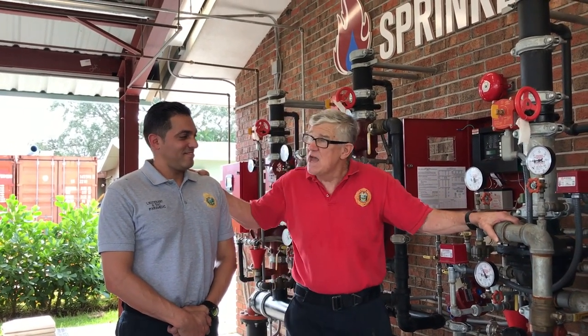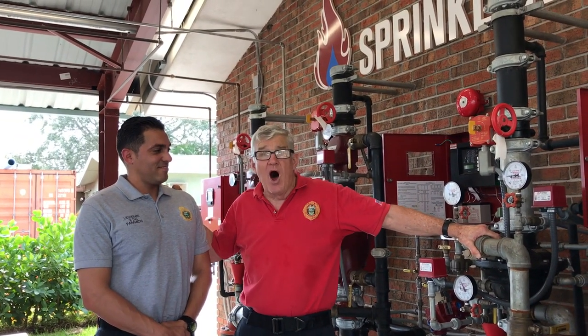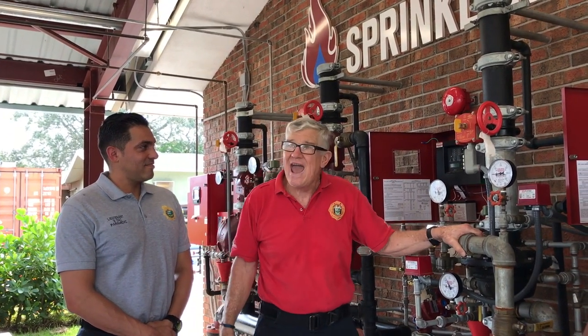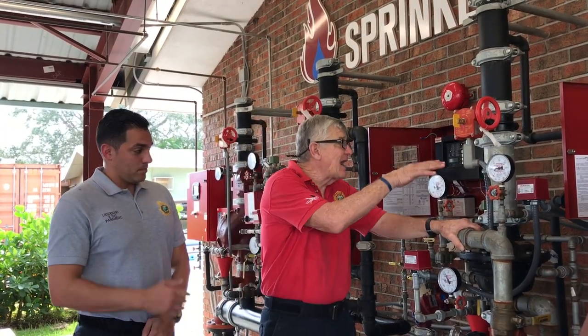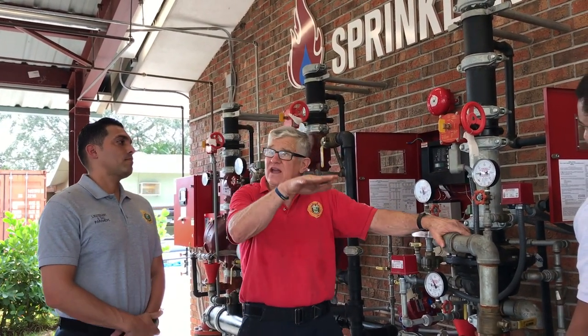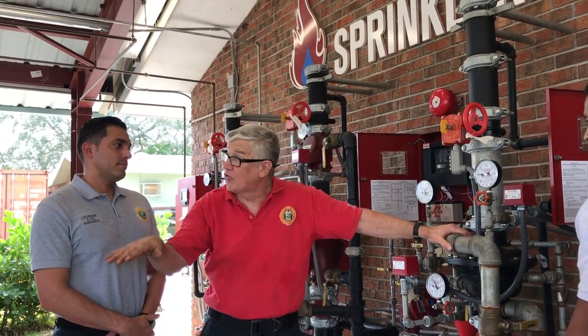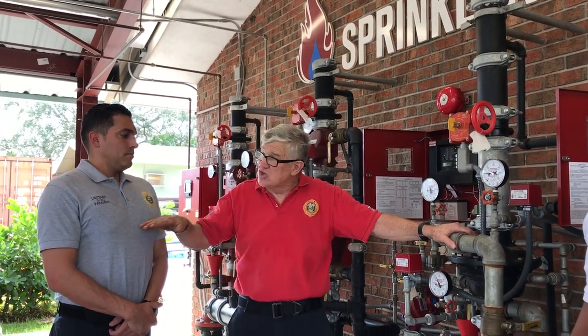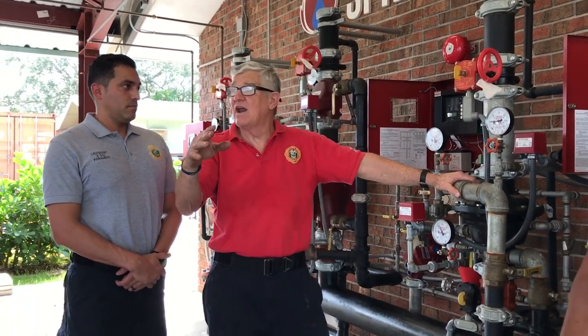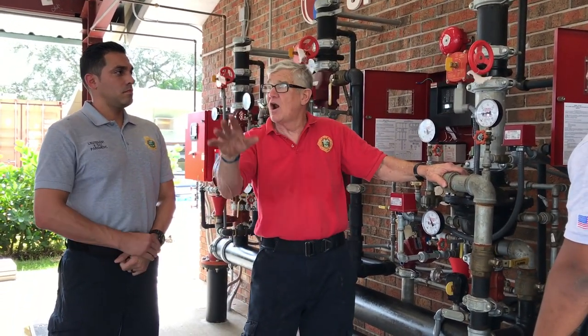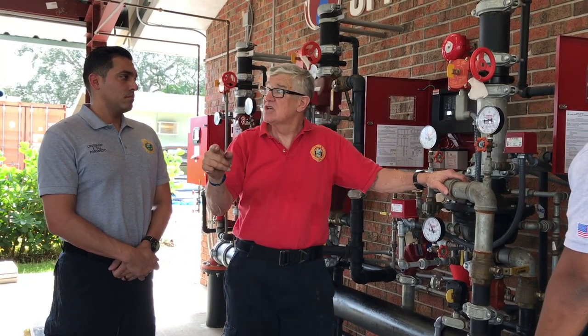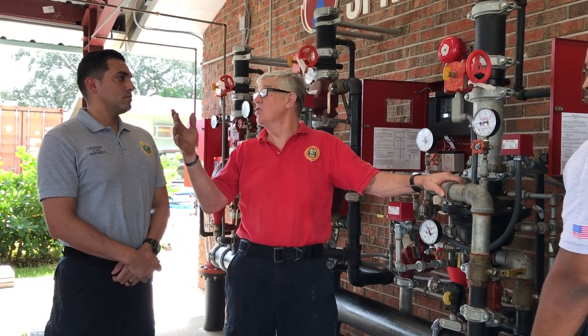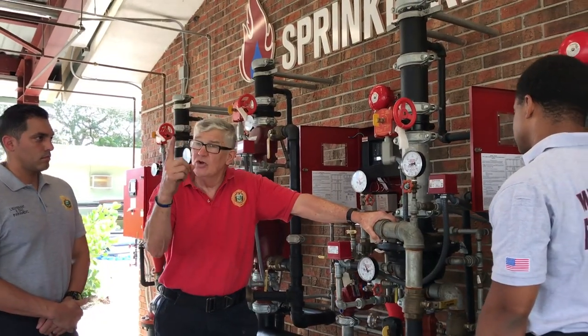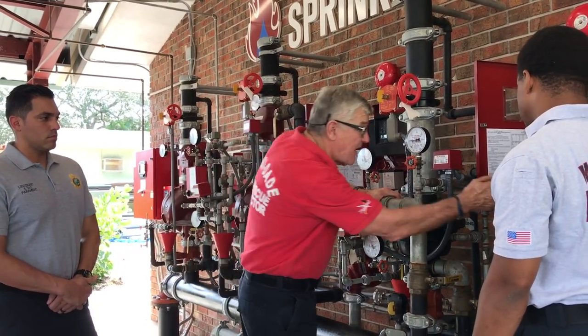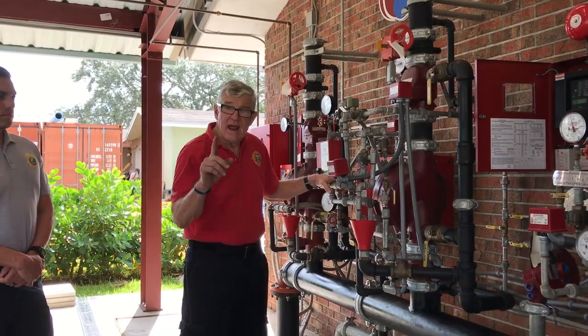So because Kenny keeps hitting the sprinkler piping, the boss installed a pre-action system. It has air in the system, but it's not holding any valves closed. It's for supervisory. When Kenny hits the sprinkler piping, air bleeds out of the system, does not flow water, but initiates a supervisory signal so the boss knows it's time to fix the pipe. Single interlock. Interlock, what do I mean by detector and activation of a sprinkler head? First is, let me take this.